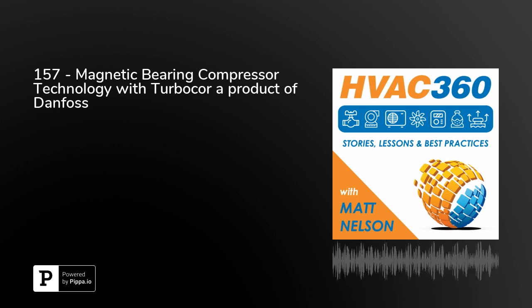So we have check valves as part of the system, and then staging valves. What a staging valve does is it allows a starting compressor to generate enough pressure to overcome the check valve pressure of the existing compressors that are currently running. So that's one of the unique things that I think would be different with a Turbocor based system versus a screw or other type of system.